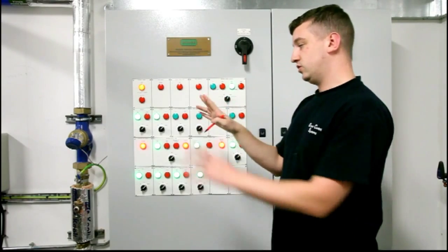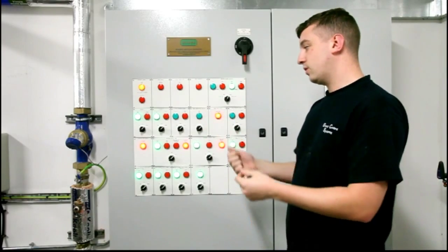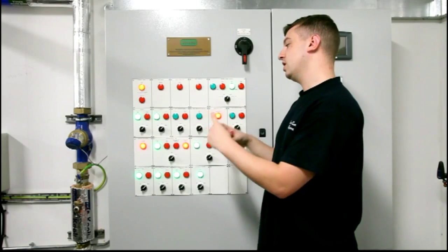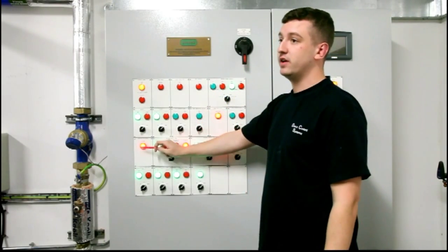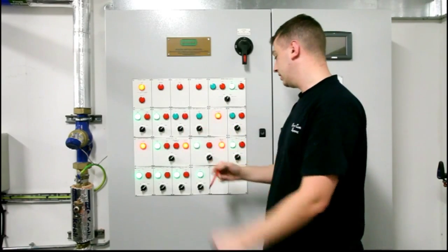As Graham said, there's two controllers that are in the kitchen office. Now, someone obviously needs to turn both of those fans on, at which point we get airflow across the supply and the extract, and then that opens the gas valve. The gas valve will stay closed until both of those controllers are turned on.